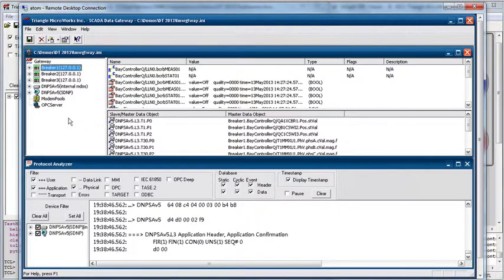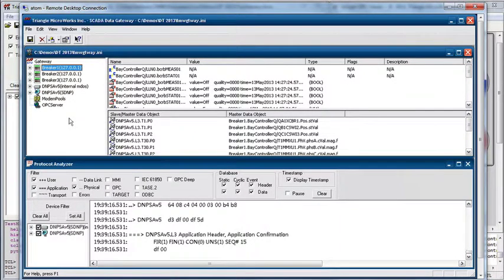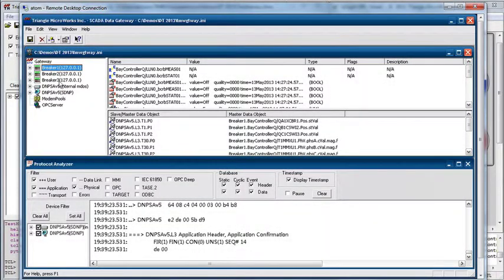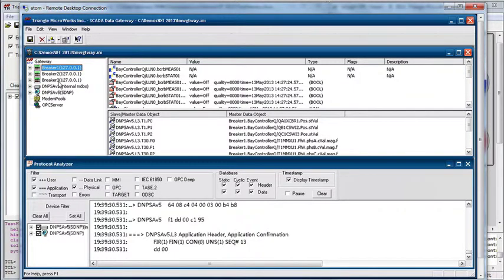On the embedded PC we see the SCADA Data Gateway. In this window, the left-hand side shows a tree indicating the various configured connections. We have three IEC 61850 client connections called breaker1, breaker2, and breaker3, each connected to one of the instances of Anvil from the previous video simulating that breaker.